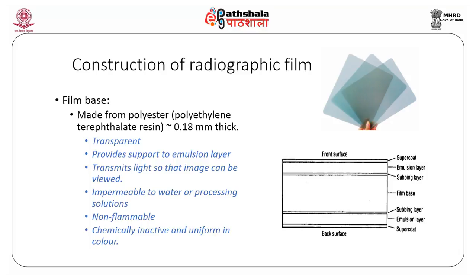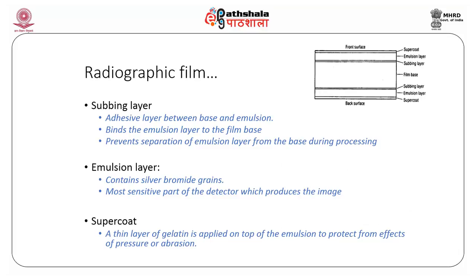Here we see the cross section of a film. The film has a subbing layer, emulsion layer, and a supercoat present on top of the film base. The subbing layer is an adhesive layer between the base and the emulsion — it binds the emulsion layer to the film base and prevents separation during processing. The emulsion layer is very important as it is the active part containing the silver bromide crystal, which is the most sensitive part of the detector that produces the image. The supercoat is a thin layer of gelatin applied on top of the emulsion to protect from effects such as pressure or abrasion.